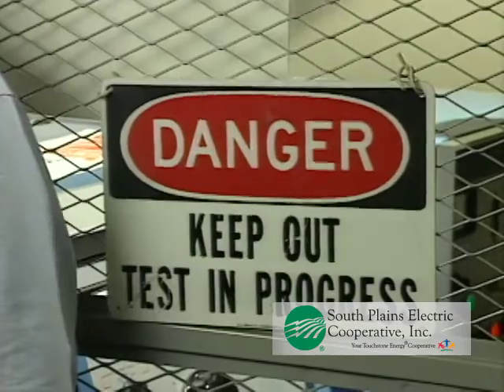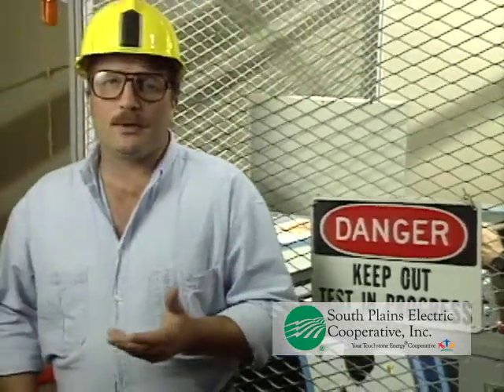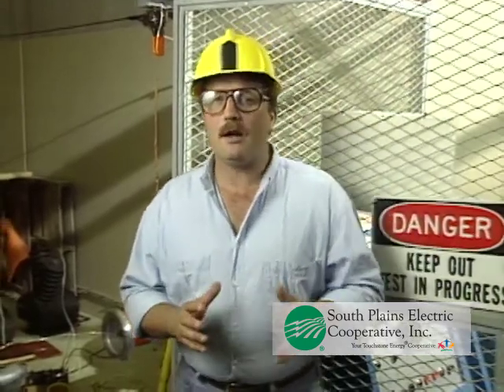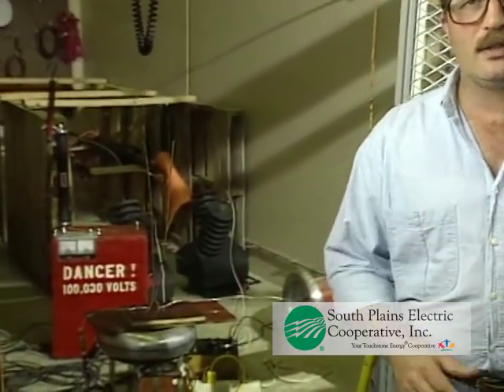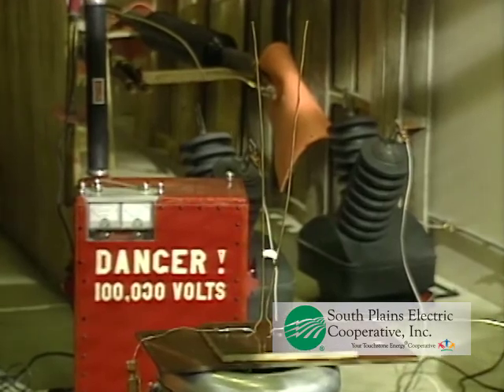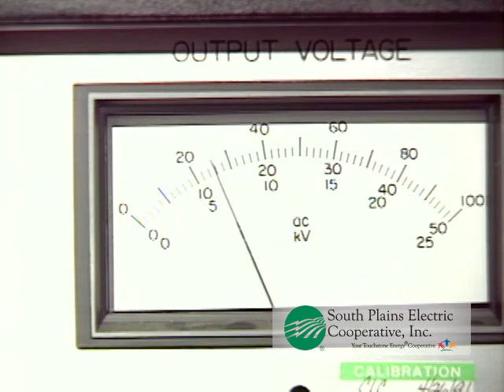Let's discuss one of the myths of electricity. Many people have the mistaken notion that electricity can jump out of the wires and travel long distances through the air. Research says that it takes 10,000 volts of electricity to jump a quarter-inch gap. Considering that the vast majority of electrical wires around buildings are energized at 30,000 volts or less, one must, for all practical purposes, come into direct contact with the conductor in order to draw an arc. However, once the arc has started, the air around it becomes ionized, thus allowing the arc to be drawn out significant distances. The point is that once contact is made, an arc will form when trying to break contact, and the size of the arc is determined by how much current is flowing from the wire through the apparatus to ground.